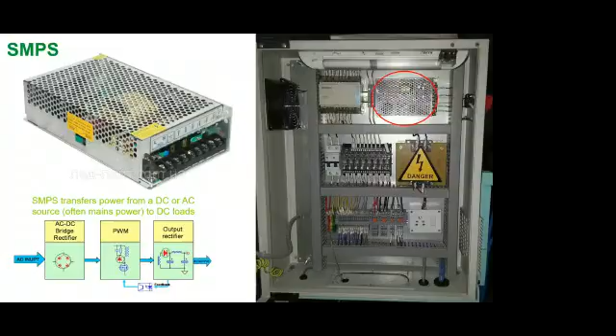As I said before, the terminal blocks are nothing but a distribution device which helps you to distribute current to various parts of the control panel. So assume this as a SMPS. This is actually an SMPS. You connect a line and neutral here, and you will be receiving a 24 volt output, and you will be taking it to the terminal block 1. What you will do is you will short all the terminals available here, and you can collect 24 volt output in every terminal's end.